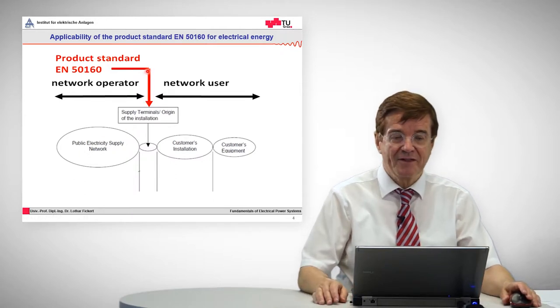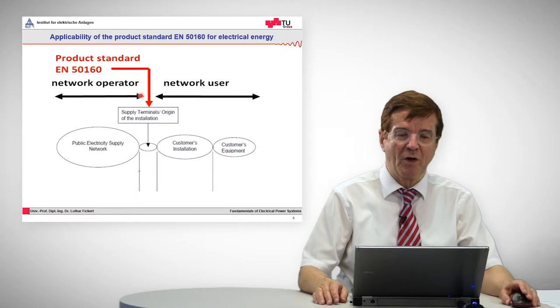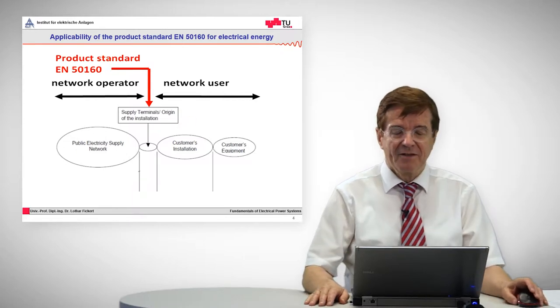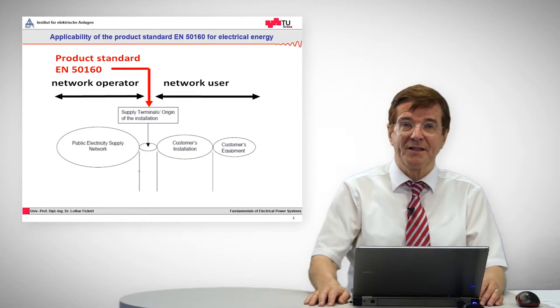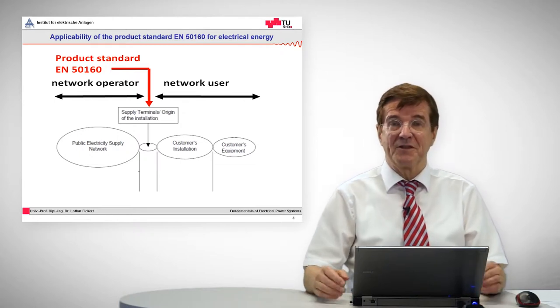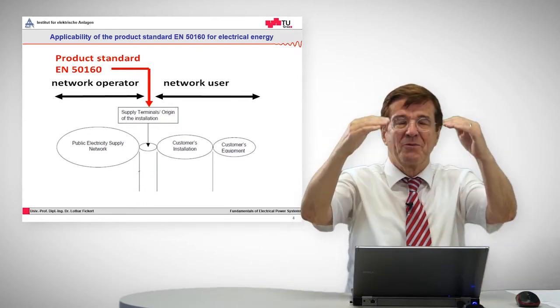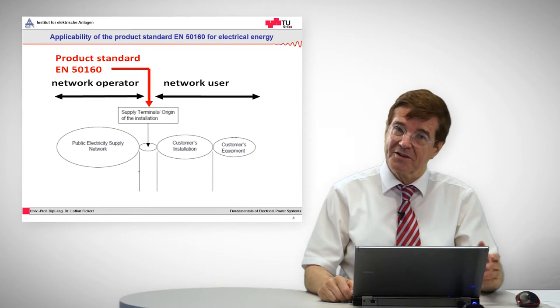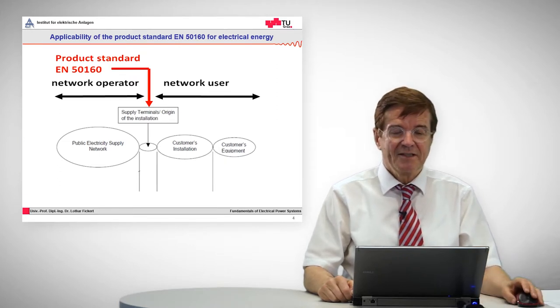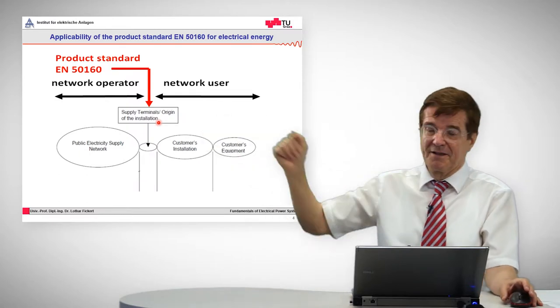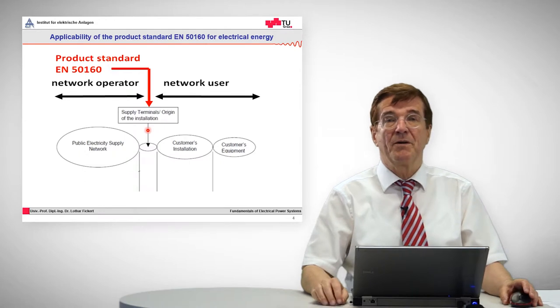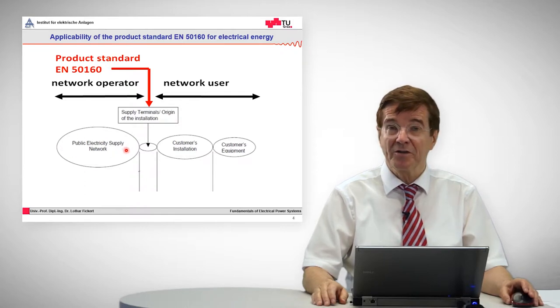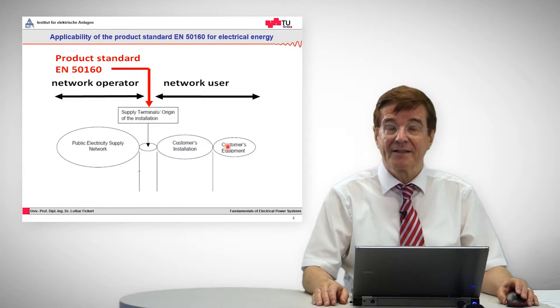There are two sides to power quality. One is the network operator, the other is the network user. There is a common rule that says the network users determine the quality of the power, because for example if we switch on a heavy load, the voltage will have a little dip. This is felt by all other consumers as a dip in their voltage, which is a feature of power quality. The supply terminals are the limit and the point where power quality is defined and measured — on one side the public electricity supply network, on the other the consumer's installation and equipment.